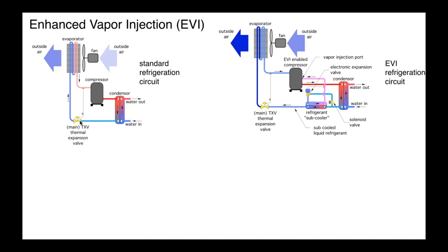Now, an EVI refrigeration circuit adds some hardware. The basic idea behind this is that we want to cool the liquid refrigerant coming off of the condenser unit. So again, we're in heating mode operation now where we've got a higher pressure, lower temperature liquid refrigerant coming out of the condenser. And instead of sending it just straight across to the TXV, we're going to go into another heat exchanger. It's often referred to as a subcooler. And the idea is we want to cool that liquid refrigerant to a lower temperature. The lower we can get the liquid refrigerant temperature, the lower we can operate that outdoor coil. And obviously, the lower we can operate the outdoor coil, the colder the climate can be and still allow reasonably good capacity and reasonably good coefficient of performance on the heat pump.